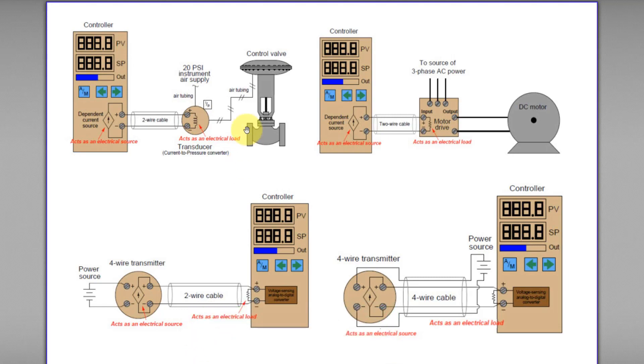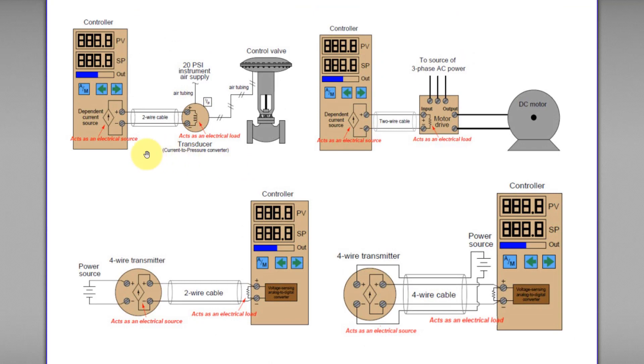Here I have a few pictures to share with you about electrical source and electrical load. Let's take this example. This is a controller, this is a control valve, and this is a transducer — an IP transducer, current-to-pressure converter. This controller provides the power source. A circuit needs a minimum of one power source and one load. Since the controller provides power, it acts as the electrical source because it powers the whole loop. And this IP transducer acts as the electrical load.